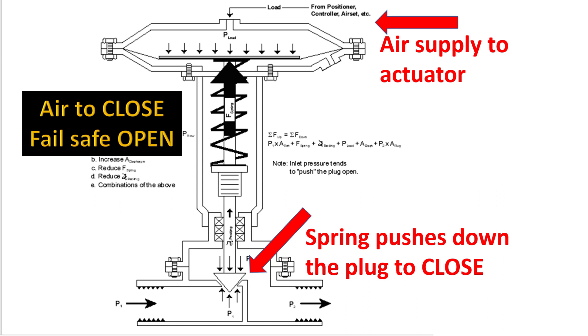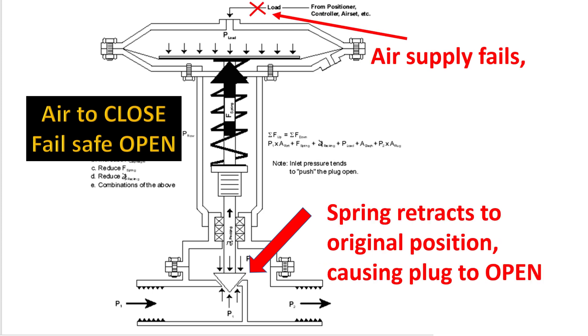When air supply is supplied to the top of the actuator, it pushes down the diaphragm, and the spring in turn pushes the plug to the closed condition — this is normal operation of the actuator. Now if the air supply fails or gets interrupted, the actuator should go to failsafe mode, meaning the valve should open during a failsafe condition.